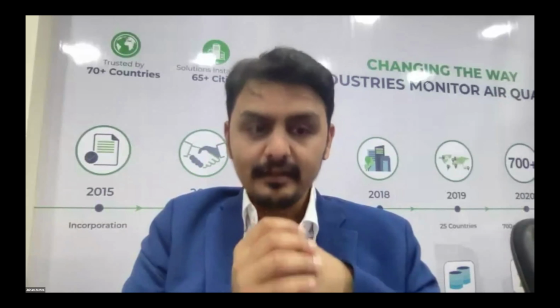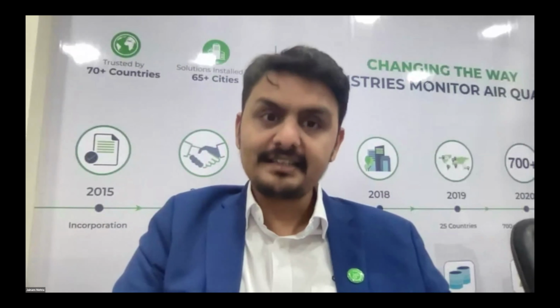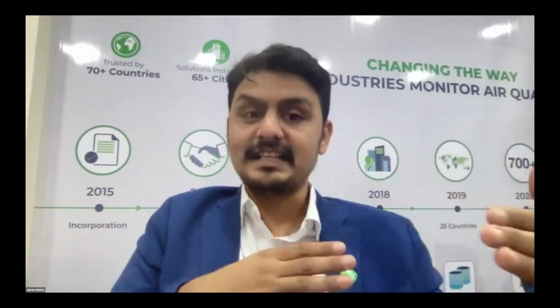Nicholas, dust calibration is very complicated. If there is a facility around you that can do dust calibration, that's amazing. But usually it's a very expensive process, and the cost is very high. So in most of our cases, people would rather replace the dust sensor than actually send it for calibration. I'm unsure about the pricing and how dust calibration works in Australia, but in most cases, because you need a wind tunnel, and then you need to import Arizona dust and all of that, it makes it a very expensive process.